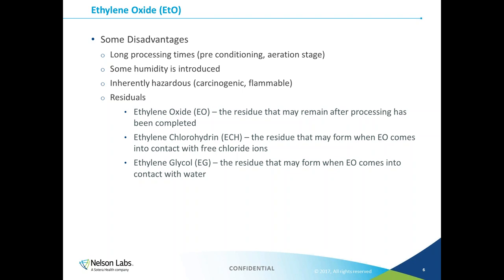A few other disadvantages to EO are possible residuals — byproducts of the processing left over after the off-gassing cycle is finished. The three main ethylene oxide residuals are: EO itself, which may remain after processing; ethylene chlorohydrin (ECH), formed when EO comes into contact with free chloride ions; and ethylene glycol, formed when EO comes into contact with water. As an interesting aside, after EO is evacuated from the chamber, the excess EO is pumped into a large chamber containing water and high humidity, which turns the EO residual into ethylene glycol — which is then recycled and used in other industrial processes.